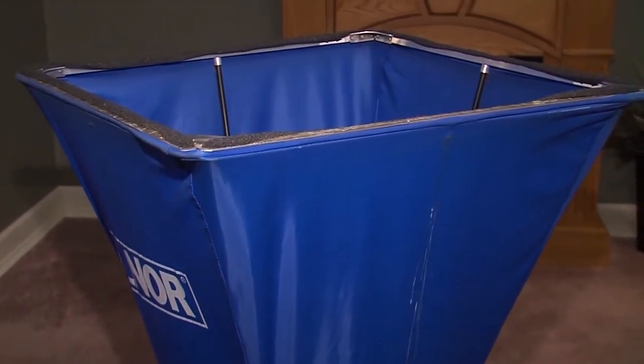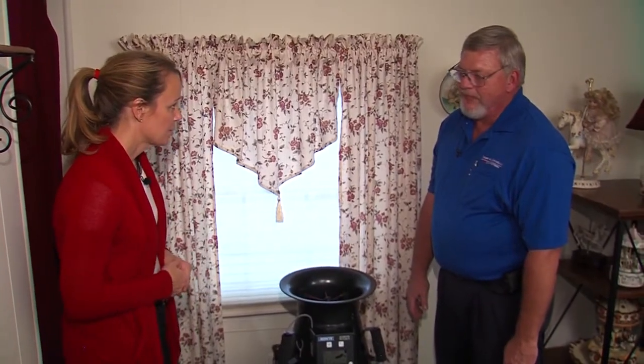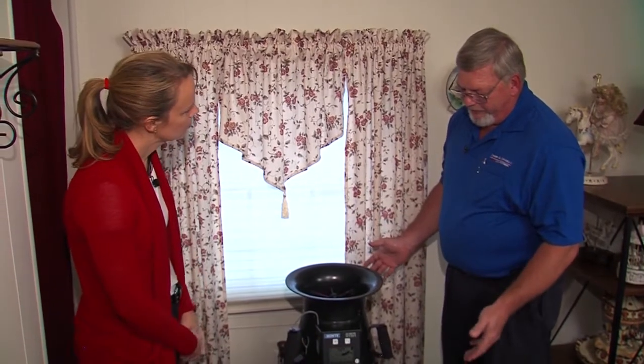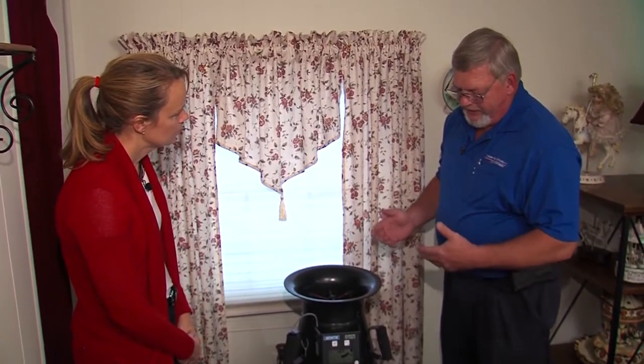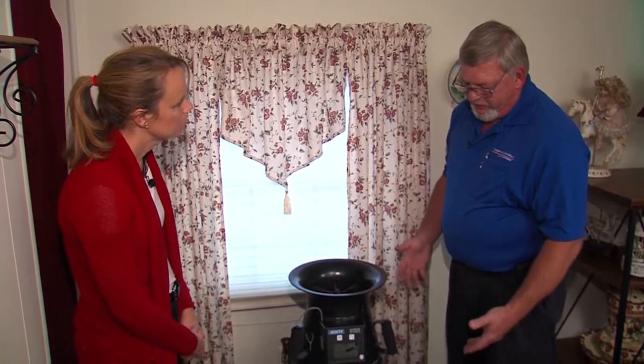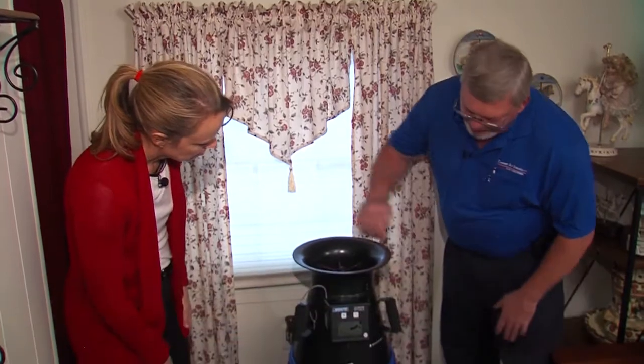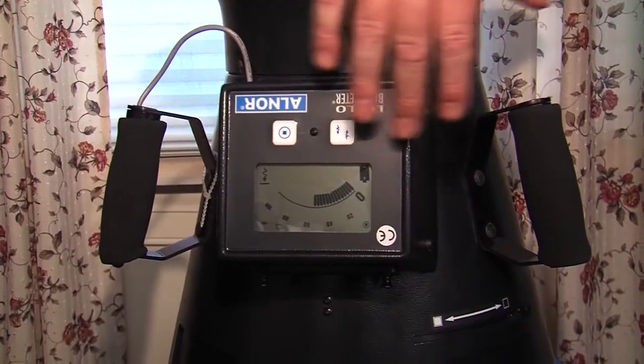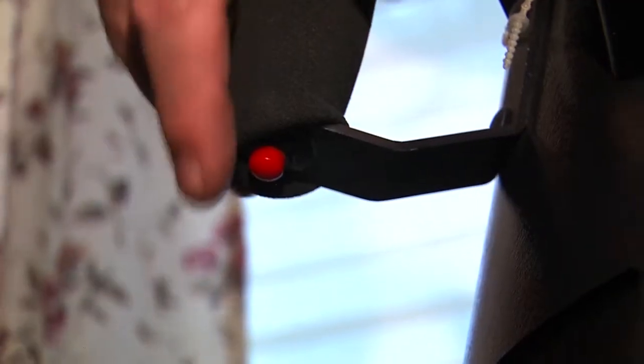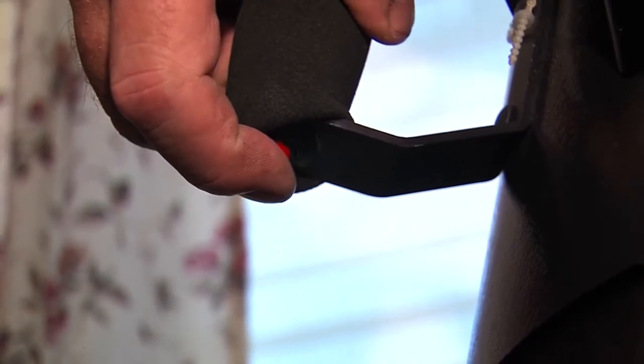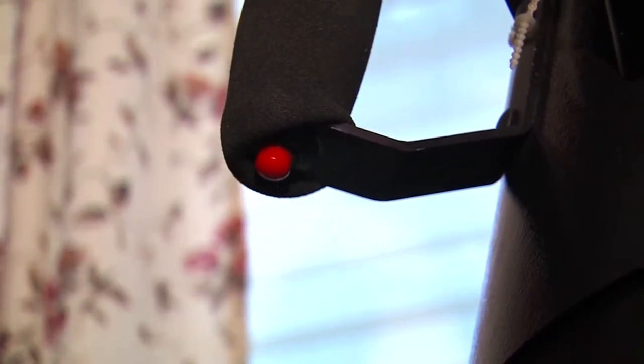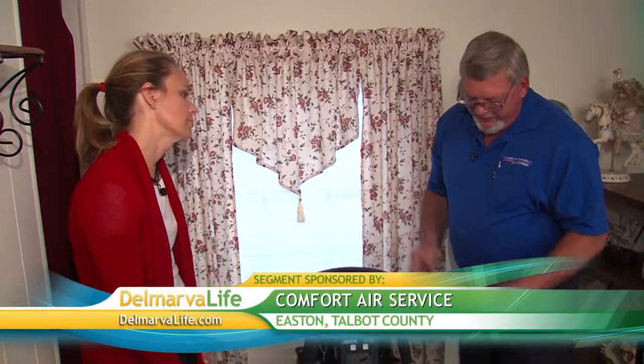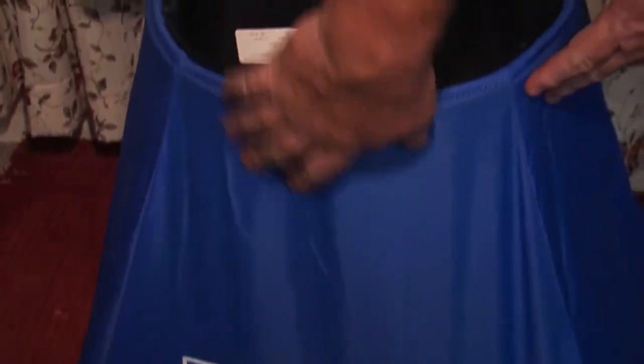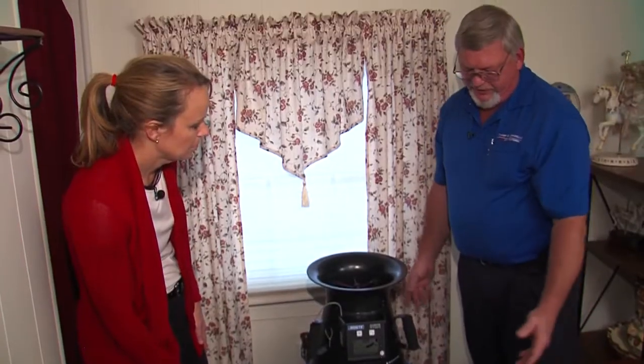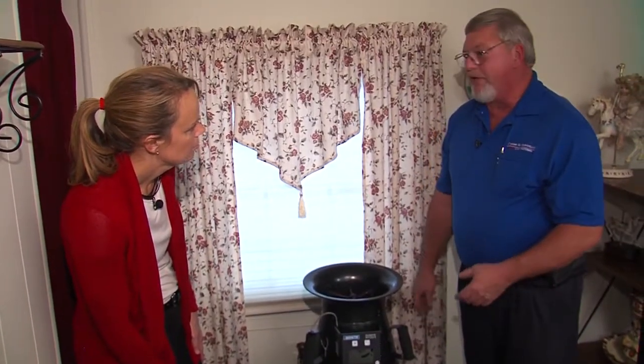So JD, this is what you actually bring into the house? Yes, this is what they call a flow hood. This is the junior version. There is a larger one, which we also use in commercial applications. As you can tell, it has a dial here that gives us official readings itself. And on top of these handles is a little click button that we use to log the actual number that comes through the vent itself. Now you can also tell it's got a canvas connector that goes around it. It comes in various shapes and sizes for all the registers and grills that are out there.